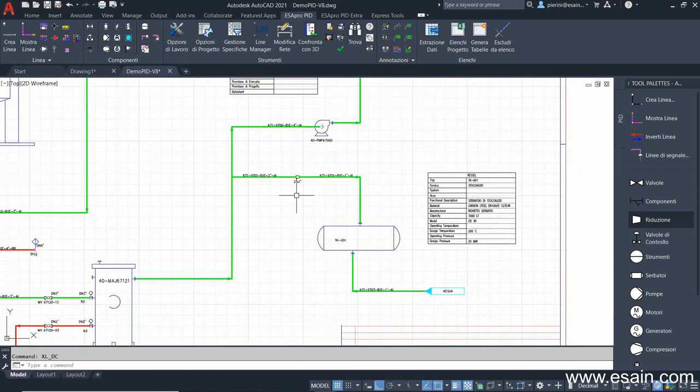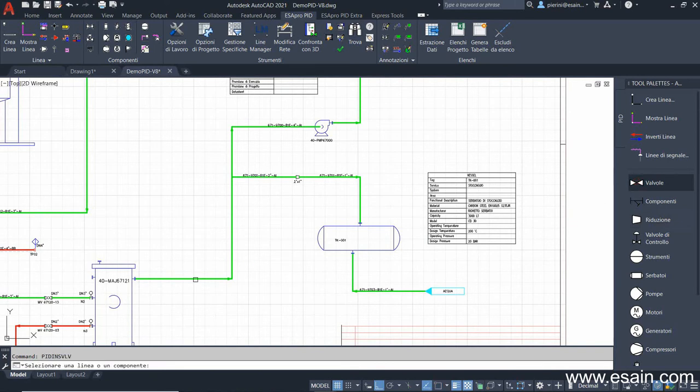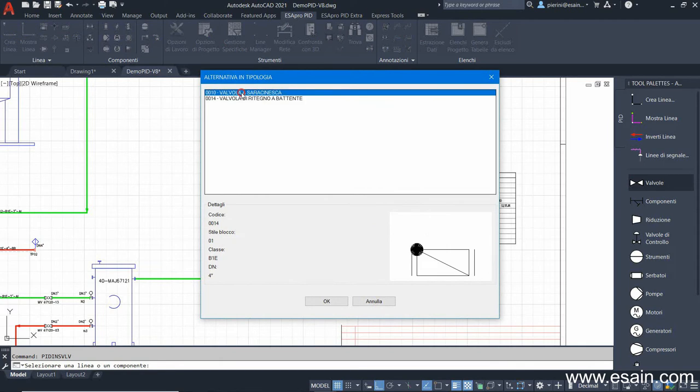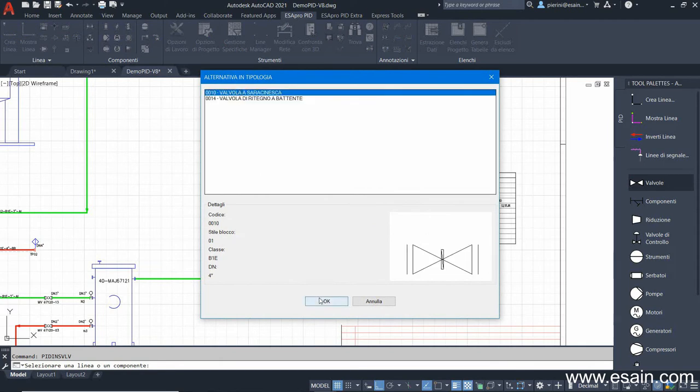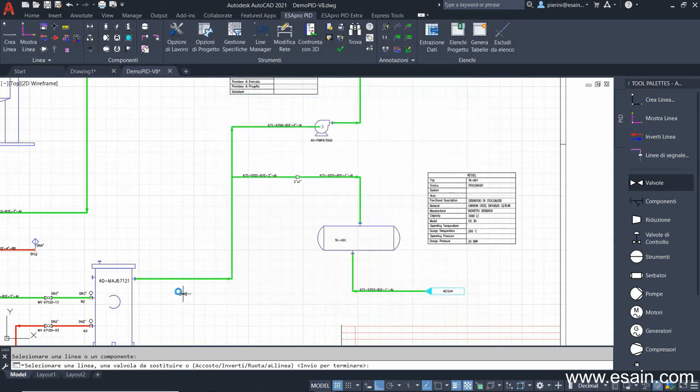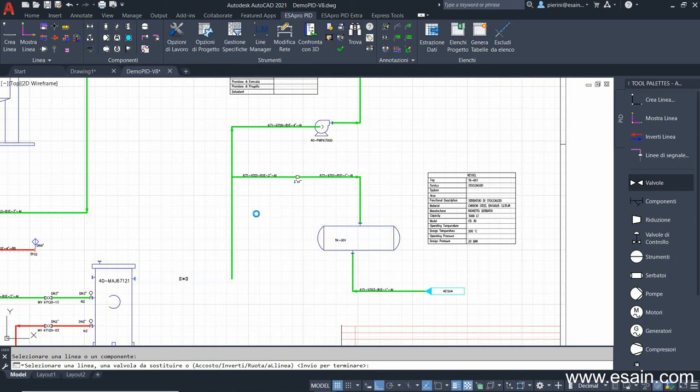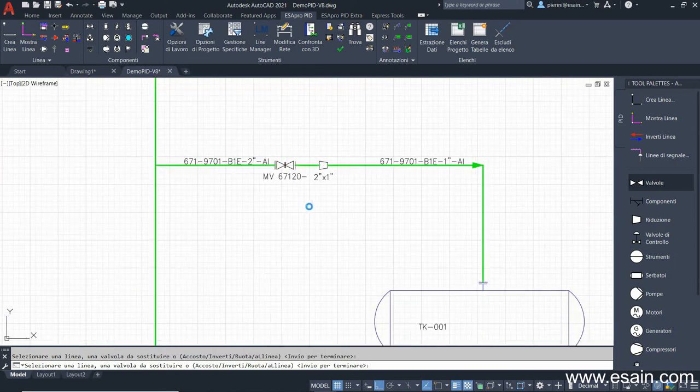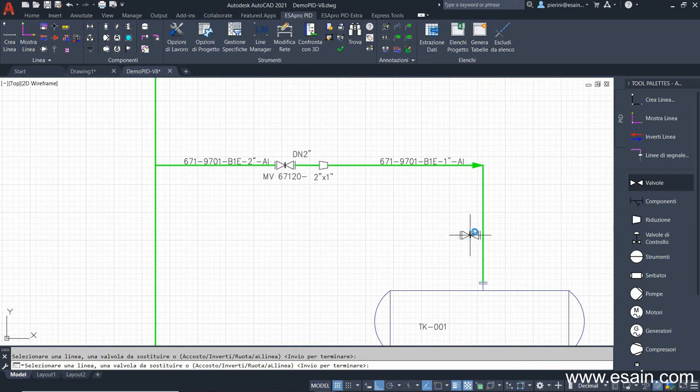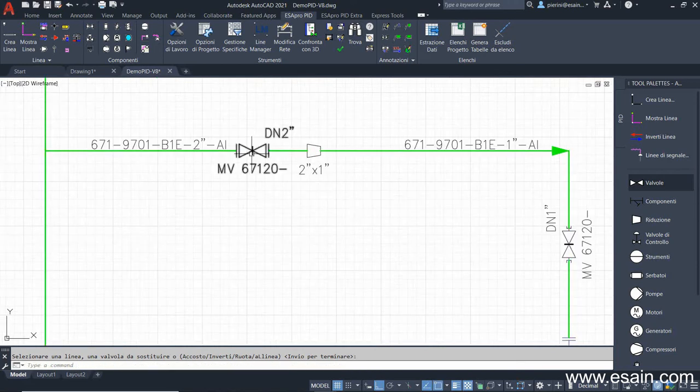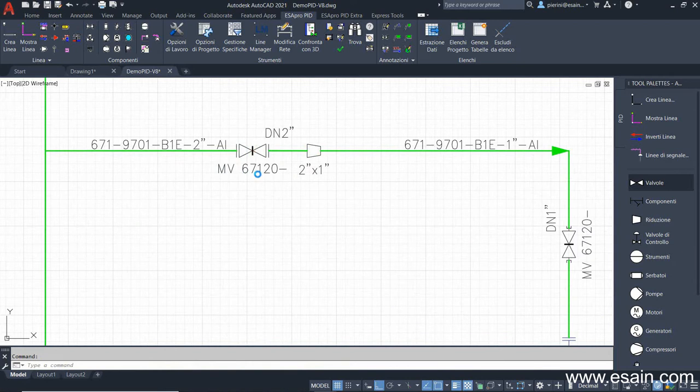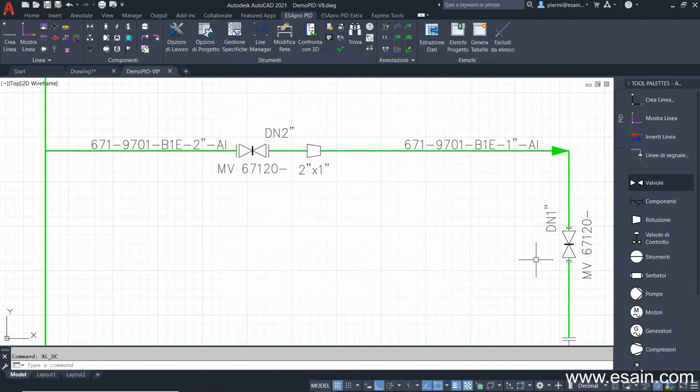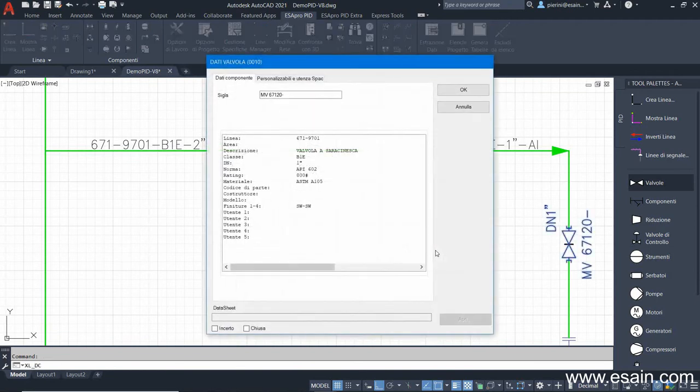Now, let's insert the valves. Pick the process line and as appropriate ID, show me only the valves compatible with that class and that diameter. We choose a gate valve. The valve is automatically oriented and cuts the line taking its characteristics from the class. We can see that it is a flanged or socket weld valve depending on the diameter. This is a flanged valve as chosen in class. And here we have a socket weld valve instead.